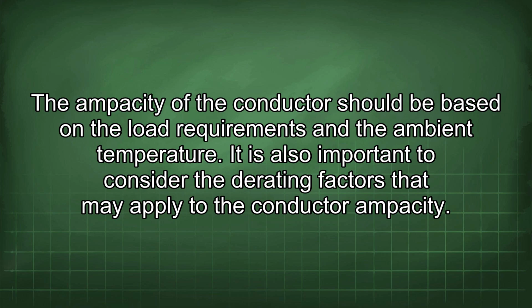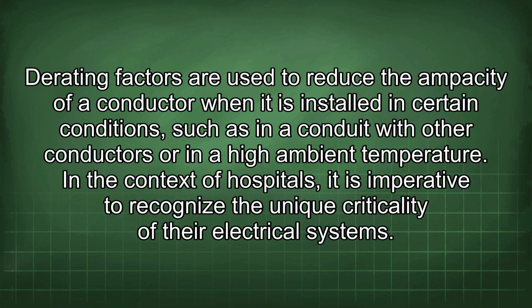It is also important to consider the derating factors that may apply to the conductor ampacity. Derating factors are used to reduce the ampacity of a conductor when it is installed in certain conditions, such as in a conduit with other conductors or in a high ambient temperature.